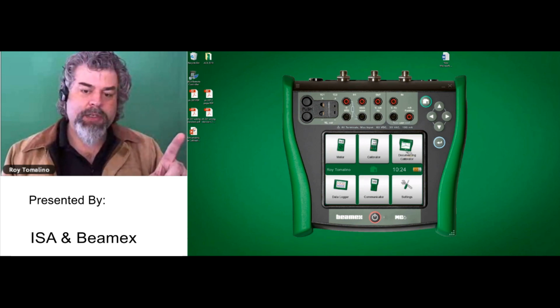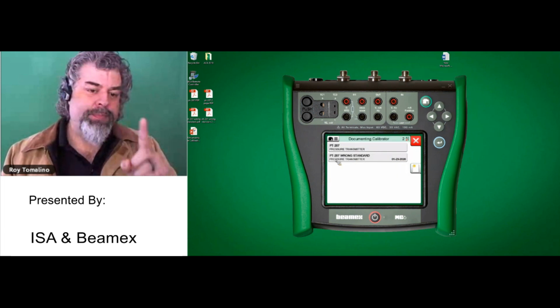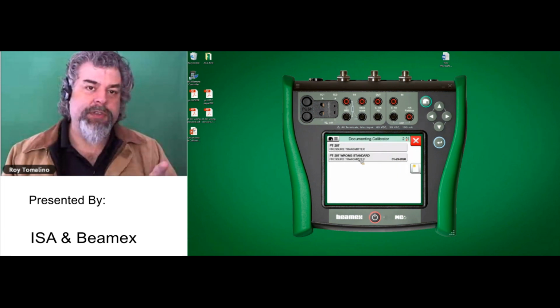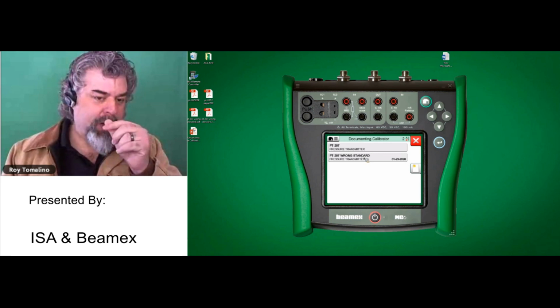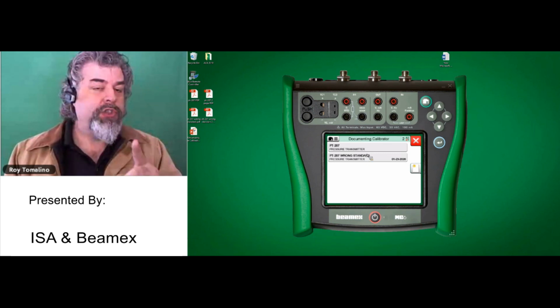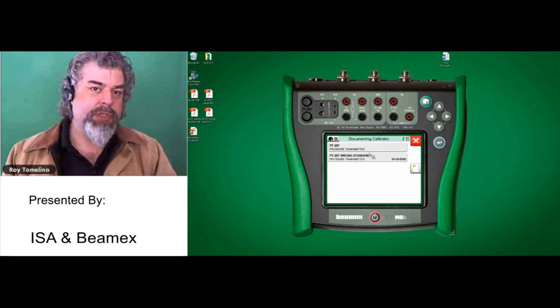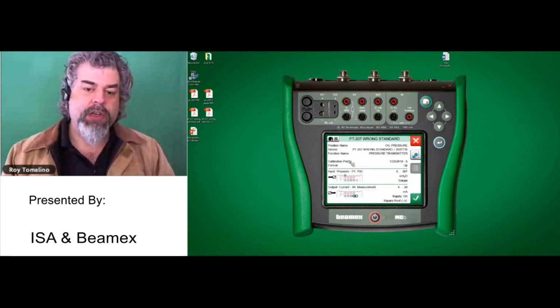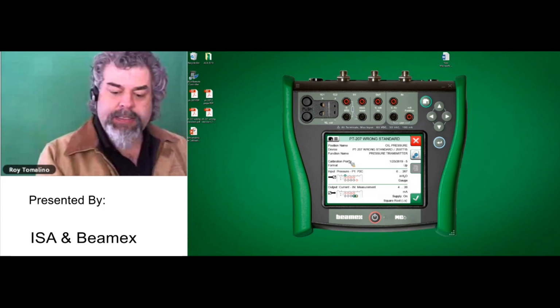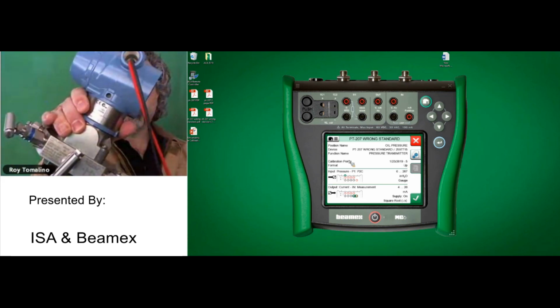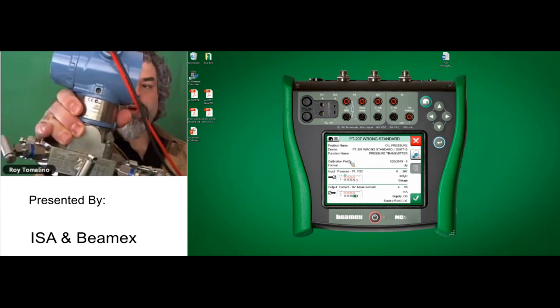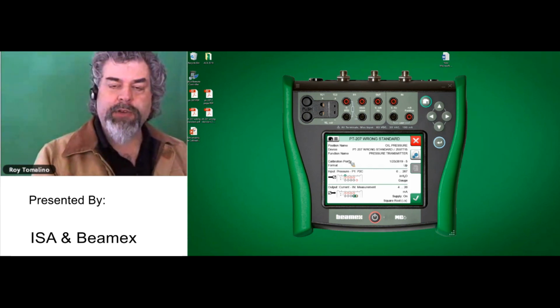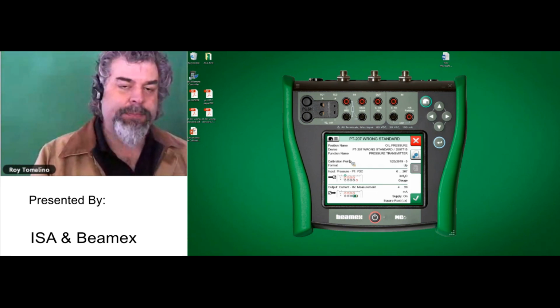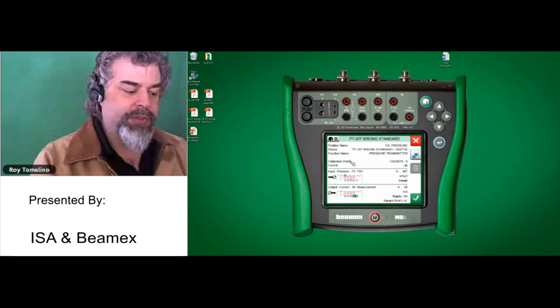This first one is our bad example. I have a PT207 with the wrong standard that I'm going to use. Where we're headed here is there's way too much uncertainty in the standard that I'm using on this one. So, PT207, wrong standard. Here's what I have: a transmitter that we're calibrating. This one happens to be a differential pressure transmitter. I am hooked up to the high side, and my low side is open to atmosphere.